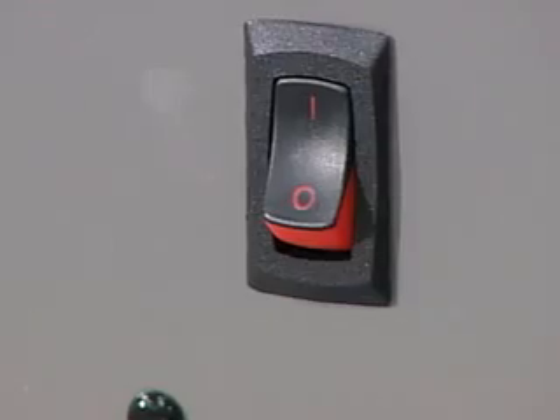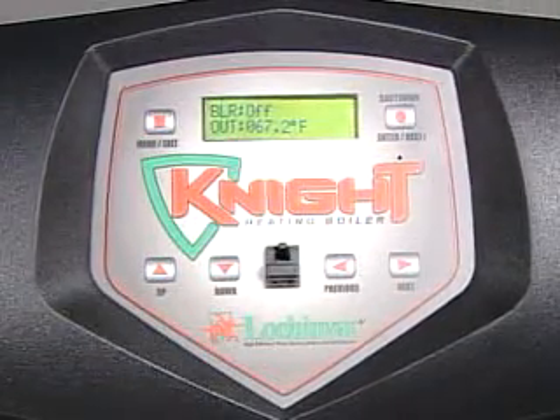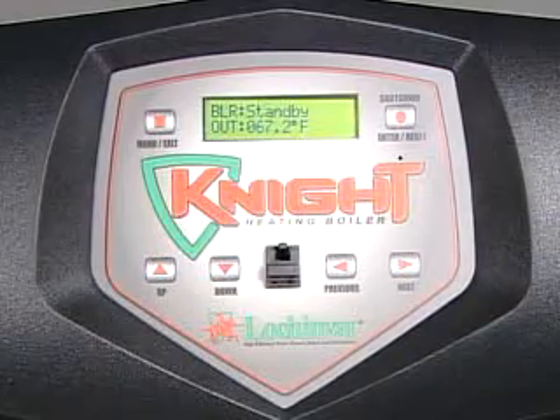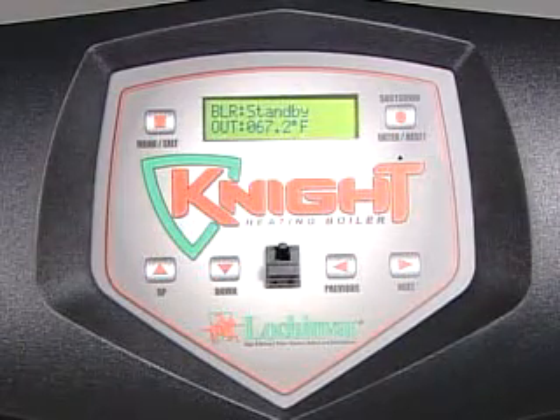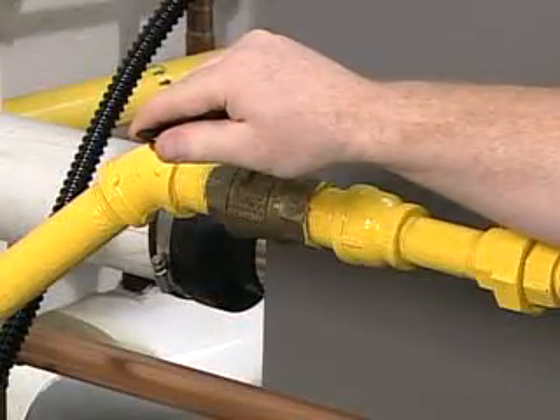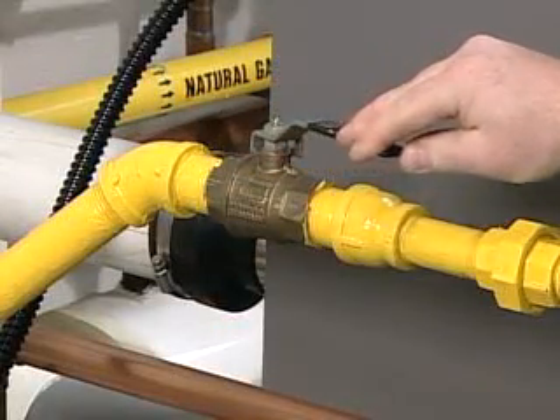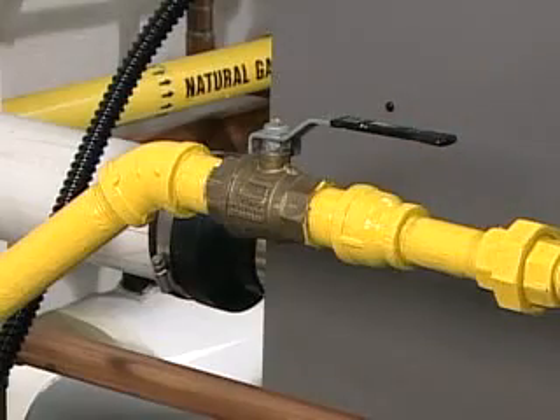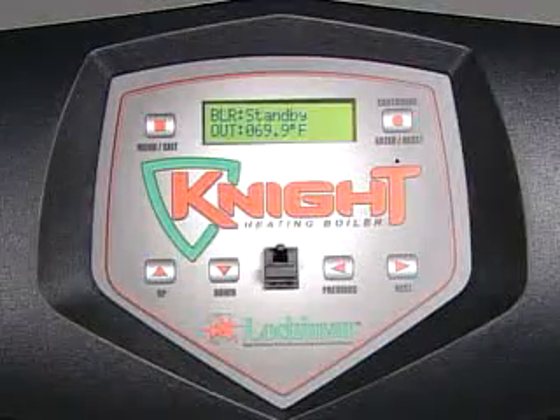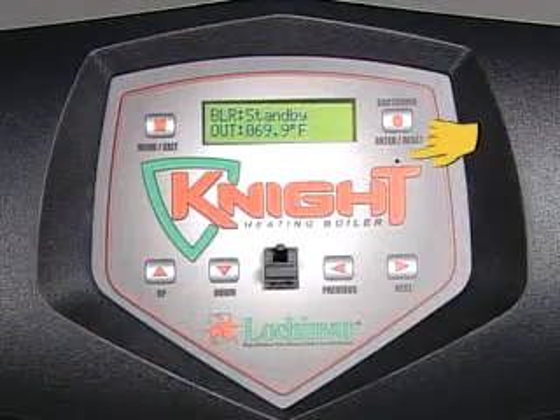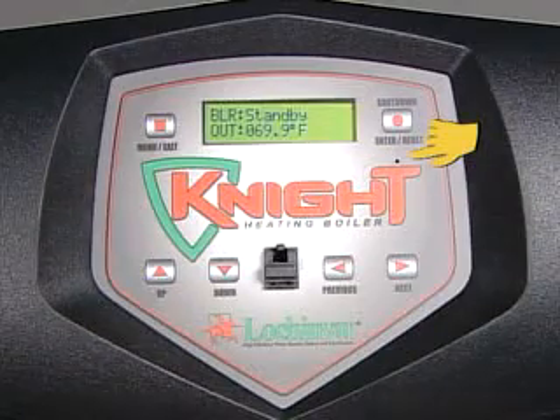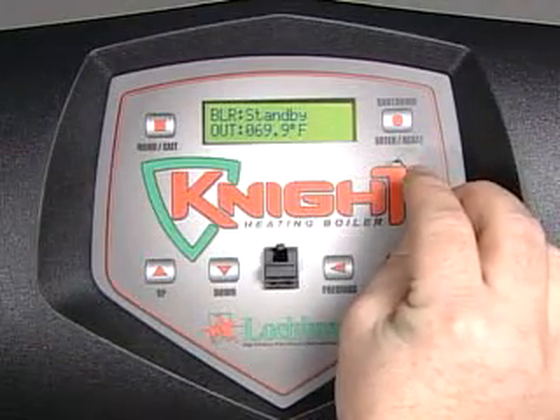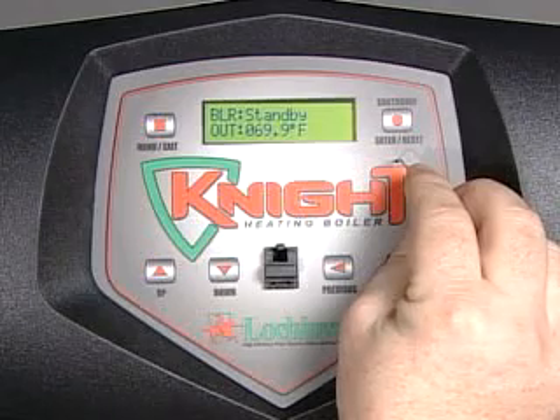Turn the on-off switch to the on position. Press the shutdown enter reset button until boiler standby is shown on the first line of the display screen. Turn on the main gas supply to the unit at the external main manual gas valve. Locate the pinhole button above the T in the Knight logo on the display. Press and hold the button for 5 seconds.